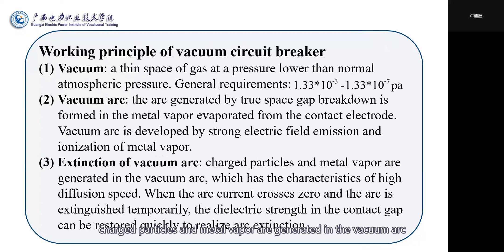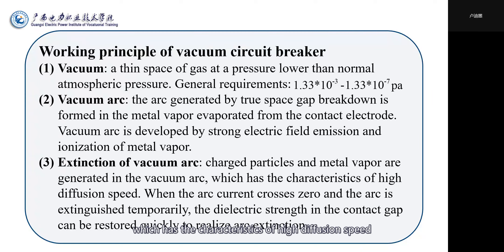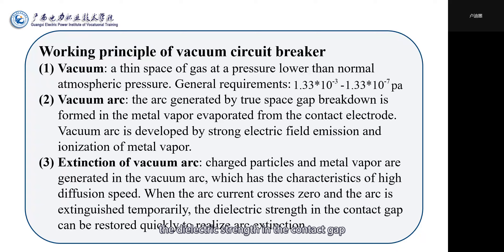(3) Extinction of vacuum arc: charged particles and metal vapors are generated in the vacuum arc, which has the characteristic of high diffusion speed. When the arc current crosses zero, the arc is extinguished temporarily. The dielectric strength in the contact gap can be restored quickly to realize arc extinction.